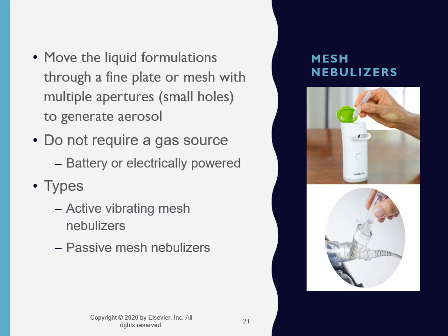Next, we'll talk about mesh or vibrating mesh nebulizers, or mesh nebs. I happen to really like mesh nebulizers. You can give a treatment on a ventilator without adding any gas into the system, because these use a vibrating mesh at the bottom in the nebulizer cup. These don't require a gas source. They're usually battery or electrically powered. The liquid formulations move through a fine plate or a mesh with multiple small holes to generate the aerosol.